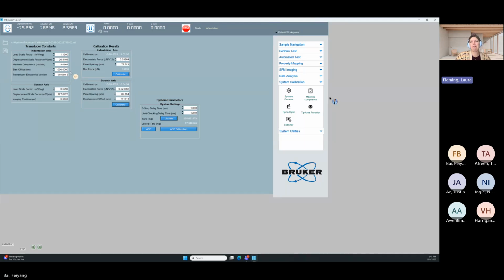And then the bias offset. If you remember during that training document, I said, this says top or bottom, but I know it's always the bottom plate. That's a physical thing. We can only get wires to the bottom plate, so the only way to control the transducer is to apply a voltage to the bottom plate, which means we can only pull down. The problem is that if you go to 0 volts, you might not lift fully off the sample surface. So we bias the center plate forward. Right now we're biased at 1000 nanometers forward, a full 1 micron. That way, during a test, when we go to 0 volts, it will lift completely up and off the sample surface. It gives us the ability to have a lift, which is also important for re-zeroing, which we will see together as we do indentation.